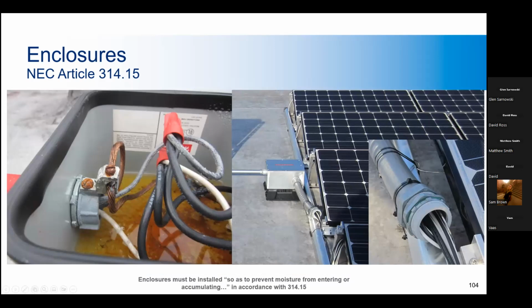And so here we have an enclosure that's not only suffering from water buildup, but the lugs on the conduit are not rated for the wet environment. You can see that they're rusting, and the wire nut terminations are also not rated for the environment. This is a location that would be well served by the installation of a weep hole to drain any excess water accumulation. And on the right, you can see that the conduit is not oriented in a way to prevent water entry. So this is a flat roof, and the conduit is kind of angled up, which basically allows for when it rains, the water will just go right in and drain down into that enclosure, which is obviously not a good thing, as I mentioned several times already. So yeah, this would definitely fail based on that.